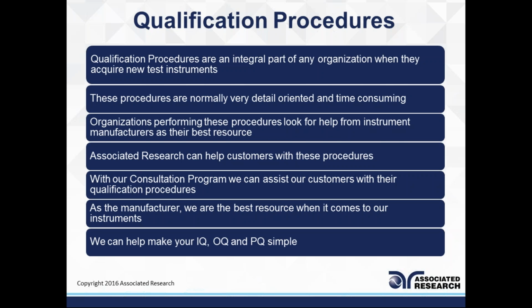Then the next qualification procedure is called OQ, which is Operational Qualification. Obviously, this comes after installation qualification. When you're done with that, you move into OQ. Once each protocol of the IQ phase has been met, OQ is performed to check that the instrument's performance is consistent with the user requirement specification or within the manufacturer's specified operating ranges. During the OQ phase, all the items in the test plans are tested individually. So this is where the instruments are actually being tested and their performance is documented.